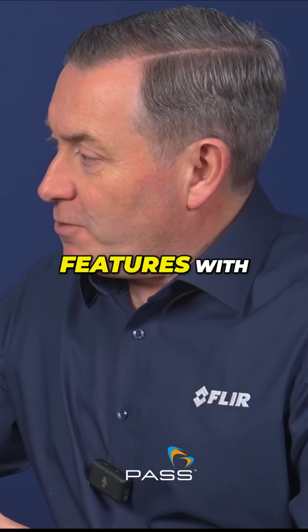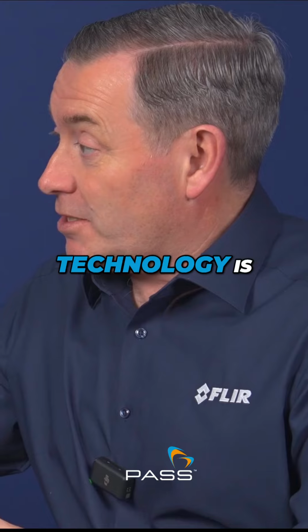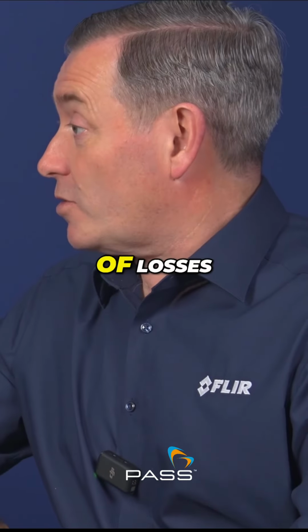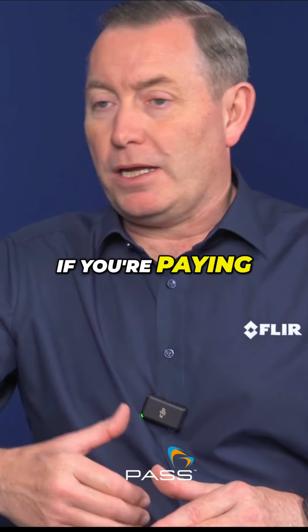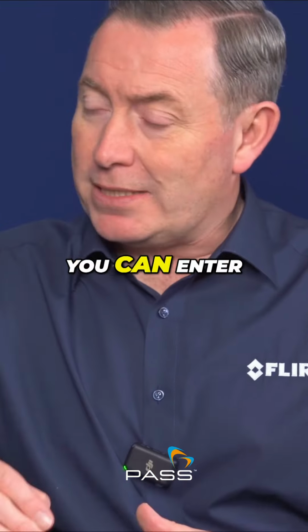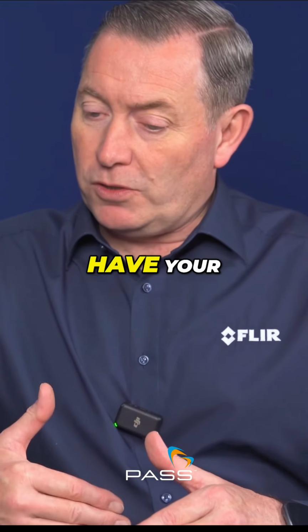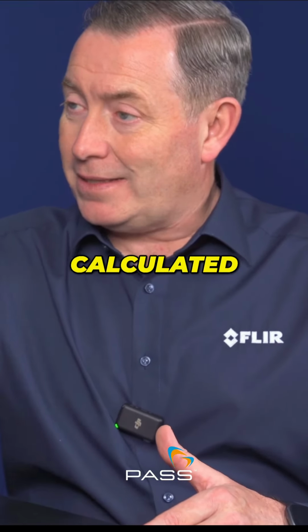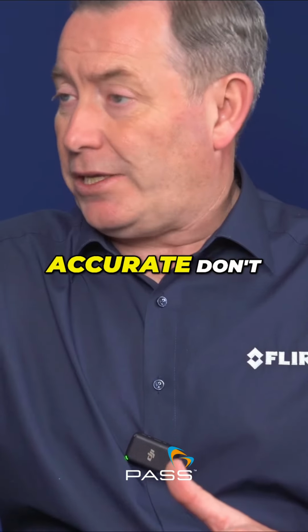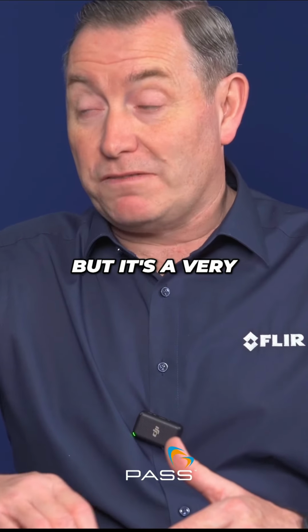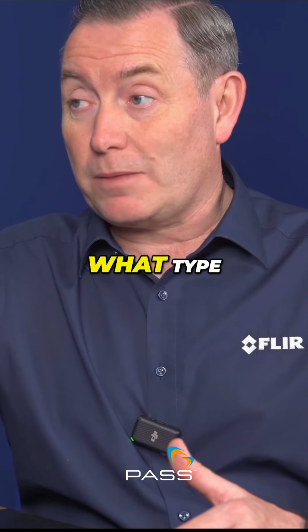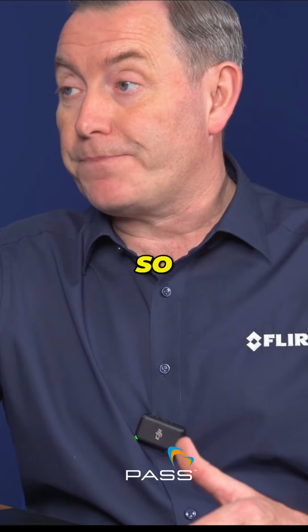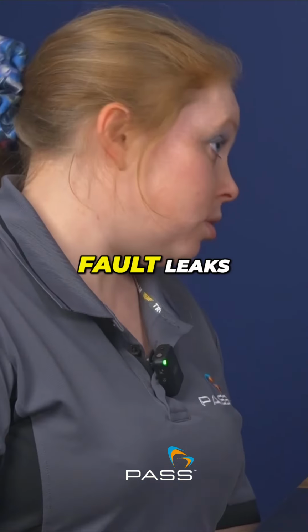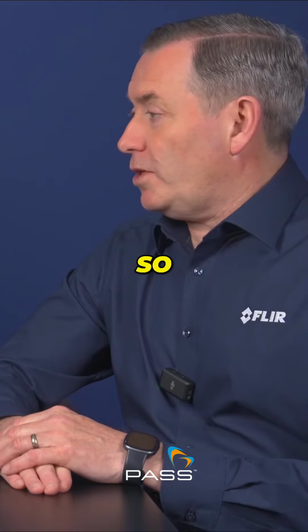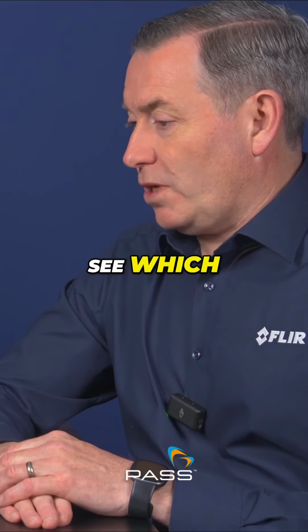So one of the key features with acoustic imaging technology is the ability to quantify the cost of losses. For example, if you're paying 20 pence per kilowatt hour, you can enter that number into the camera, and then the quantification cost is calculated internally within the device. Don't get me wrong, it's not to the penny, but it's a very good indicator of what costs are being lost over a year. So it's good for prioritising faults, leaks that need to be fixed. You can essentially see which leaks are the worst.